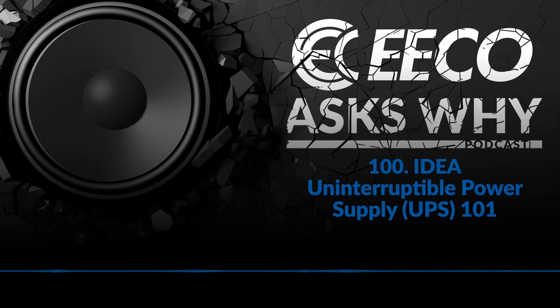Yeah, that's more common in places with data rooms and data servers and things like that, but it's also great for any kind of industrial application. So a maintenance bypass is exactly what it sounds like - you bring your mains voltage into that maintenance bypass, then go from the maintenance bypass to your UPS, and then from your UPS back to the maintenance bypass, and then out to all of your loads.